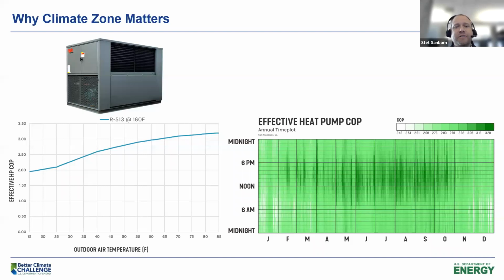Most manufacturers, you can extract this curve from them. It's often painful, but it's doable. You can get this performance curve and map it over outside air temperatures, then use that relative to our actual weather file.